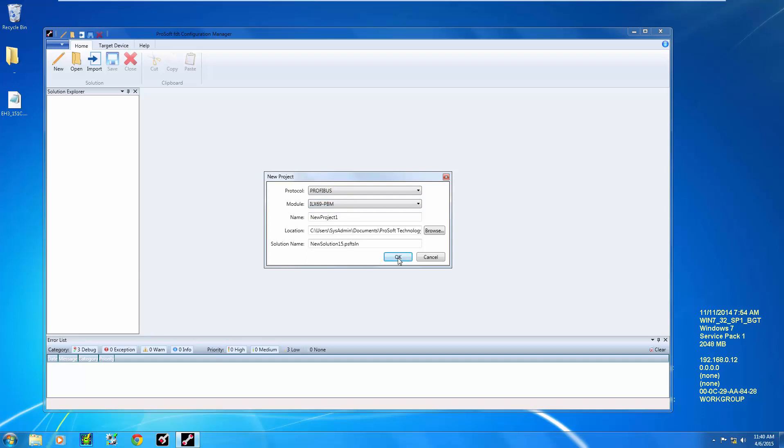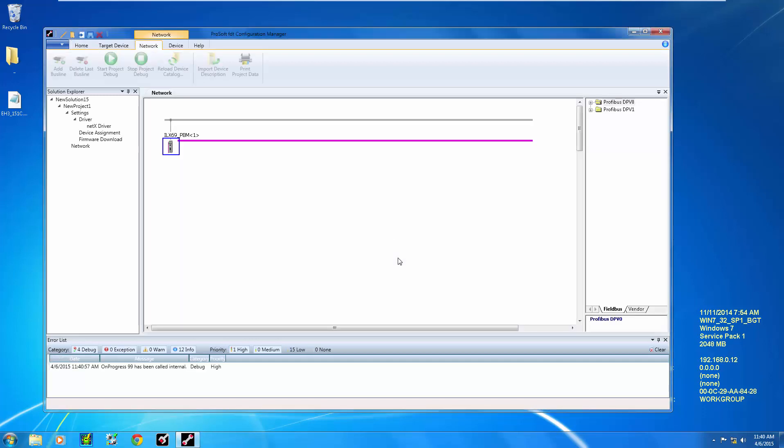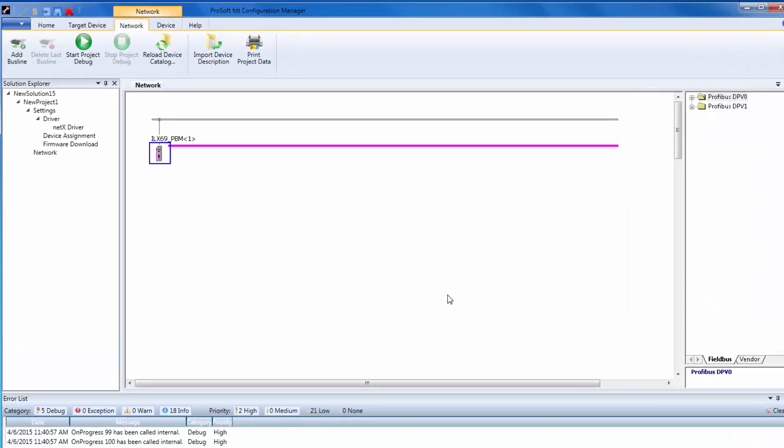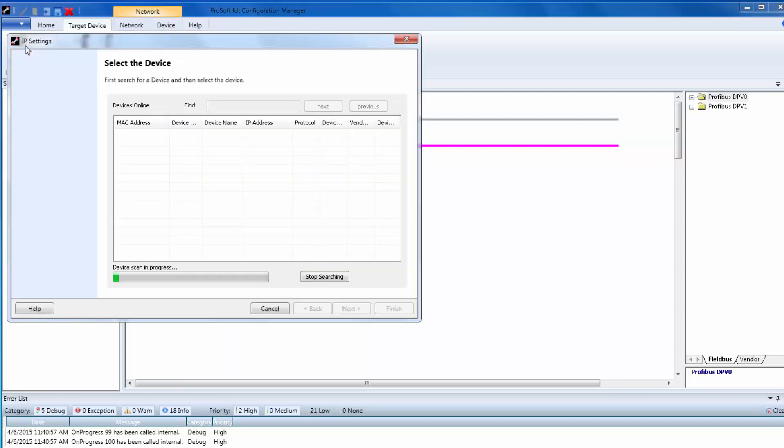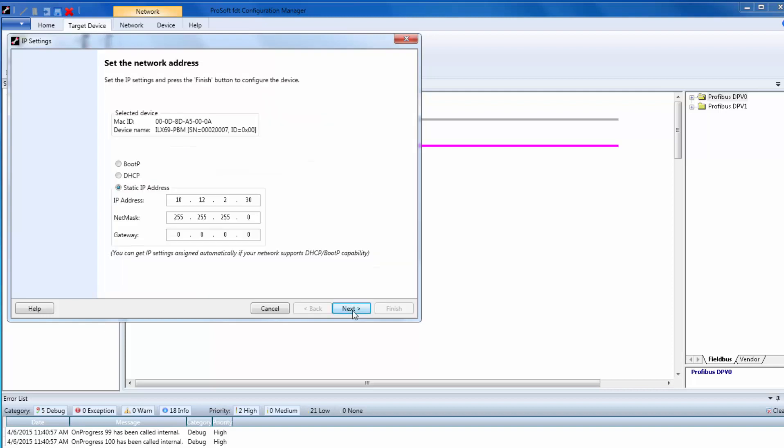First, we will set up the IP address. To do this, the PBM must be on the same physical network as your PC. Click on the Master, then click on the Target Device tab. Then click on IP Settings. This will automatically browse your network for this module. Verify the MAC address, and then click Next. Give your module a valid IP address and then choose Finish. If you do not know a valid IP address, you may want to contact your network administrator.